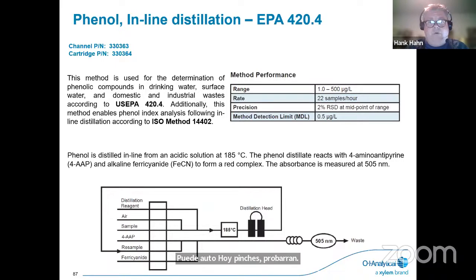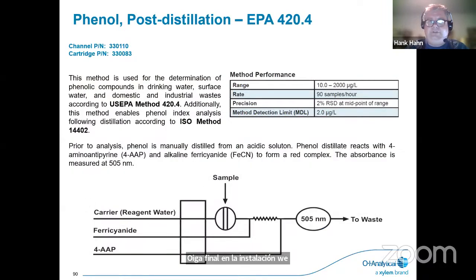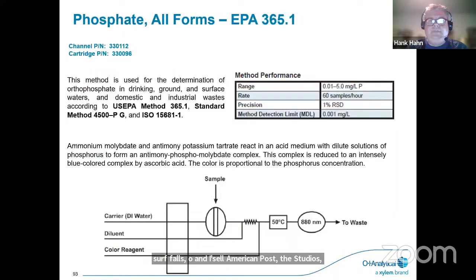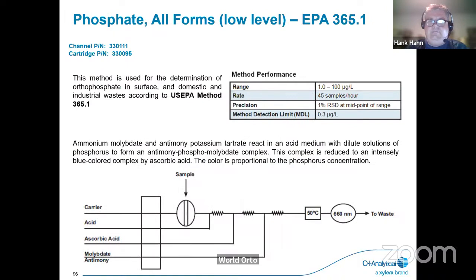We've got phenol inline distillation with the distillation head. And we also have phenol post-distillation as well. And that also follows an ISO method in the post-distillation chemistries. We've got all forms phosphorus. And by the all forms, you can configure that for total phos or orthophos as needed. The low level orthophos is where we use a different sized flow cell to achieve the low detection levels.